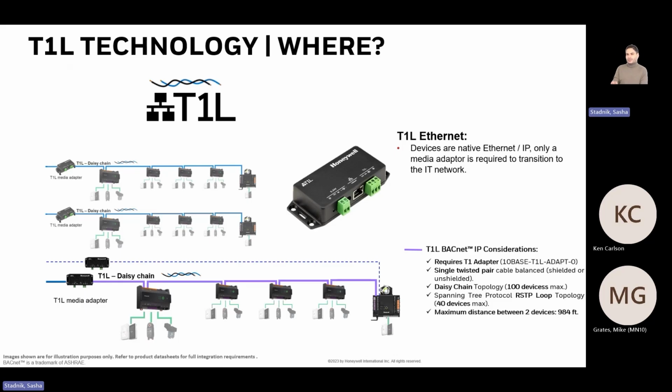From the chip to the processor of the controller, that is for the manufacturer to use. So, for example, Delta or whomever follows us could potentially not use that information for anything and release a T1L controller that cannot fail over. Even though it's in the standard, that doesn't mean the manufacturer must use it. The chip manufacturer is required to expose that information, but it's up to the controller manufacturer to use it as they please.